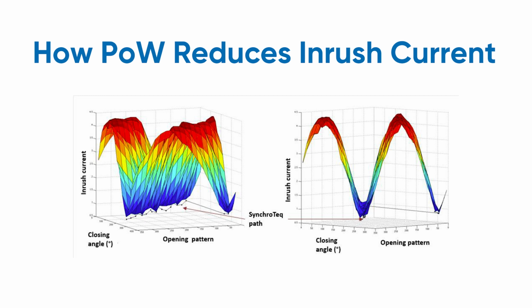It can calculate the residual flux in the transformer core, and it can then calculate the optimum closing angle for the circuit breaker so that we don't take the transformer into saturation. This is shown here as this interesting graphic. As you can see, every closing angle has an opening angle that would result in low inrush current. Effectively, the y-axis there is inrush current, and we're targeting these blue zones. So for every opening angle that you could possibly have between 0 and 360 degrees, there's an optimum closing angle. That's what the SynchroTeq algorithm is doing, and that's how it's allowing us to alleviate these issues.